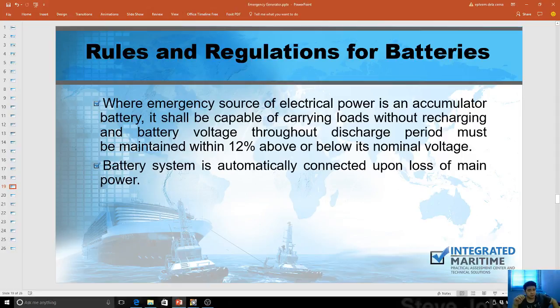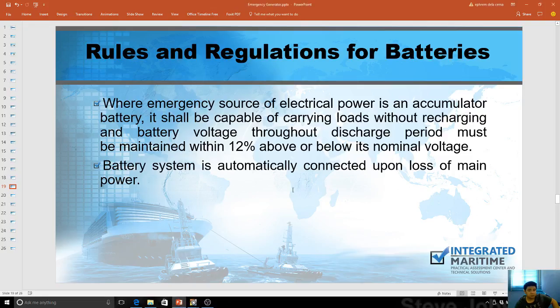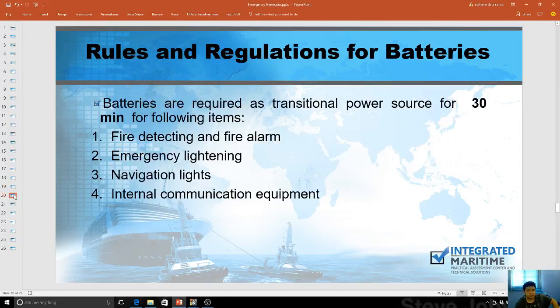For batteries: when batteries are the emergency source of electrical power, the accumulator battery shall be capable of carrying loads without recharging, and the battery voltage throughout the discharge period must be maintained within 12% above or below its nominal voltage. So when electricians check that specific battery, it should not deviate more than 12% of its nominal voltage — for example, 24 volts times 0.12. Battery systems are automatically connected upon loss of main power and are required for transitional power for 30 minutes, covering fire detection, emergency lighting, and navigation lights.